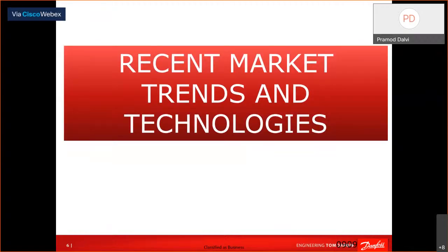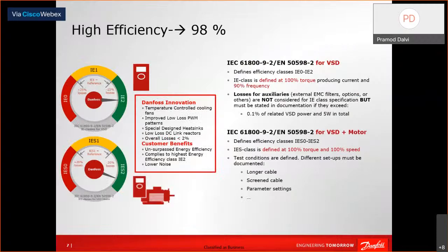For recent market trends and technology for these applications, I have divided our presentation into two parts: one is efficiency and the second is reliability. High efficiency is a very important feature of our drives, which is 98%. We achieve it through temperature controlled fans, low loss PWM patterns, specially designed heat sinks, and built-in low loss DC reactors. Overall, we get around 2% losses, so we can achieve 98% efficiency.